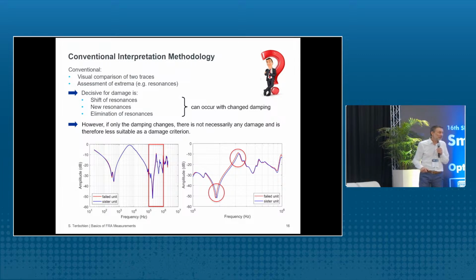If the transformer is still in the warranty time, of course, the operator would say this is not okay, and the manufacturer will say it's okay, it's very fine. So you see that this visual interpretation is questionable. It depends on the point of view. So what we are looking for is an objective interpretation of these curves.